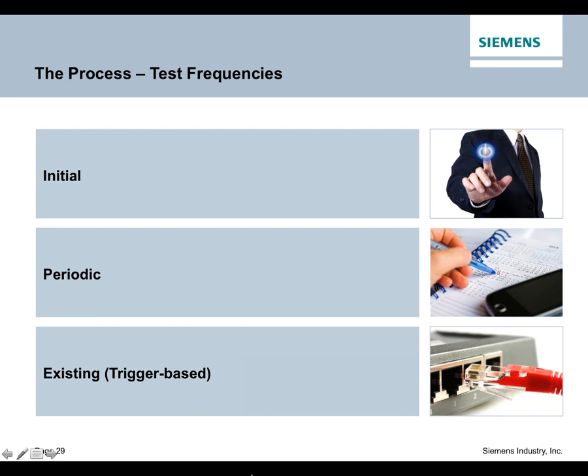So here comes the cool stuff. When do we need to do this? It starts out, in the most basic element, when the building is actually being installed. When the building is being built, on the initial aspect of it, you need to do an integrated test per NFPA 4. The next slide will show that in a little more detail. That's required by and during the commissioning process. So when you commission your building, you've got these things going forward.